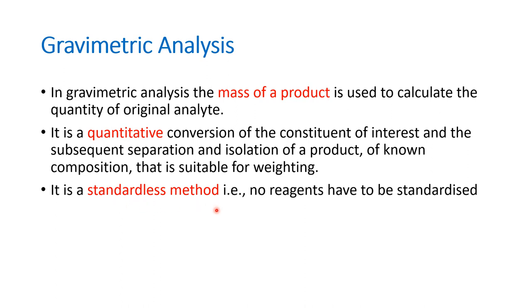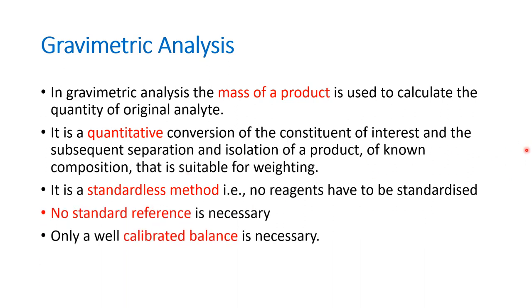It is a standardless method — no reagent has to be standardized. Very importantly, what is necessary in gravimetric analysis is a calibrated balance, because all parts of the analysis are done through weighing only. The samples will be weighed and the crucibles will be weighed. In every step of gravimetric analysis, it is the weight of the substance that matters, so a well-calibrated balance is a necessity. There is also a possibility we can test the purity of the product.